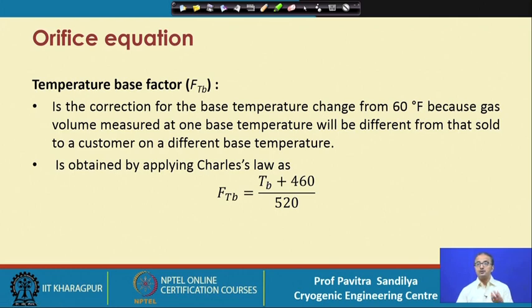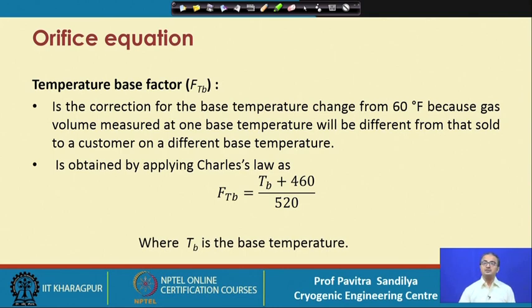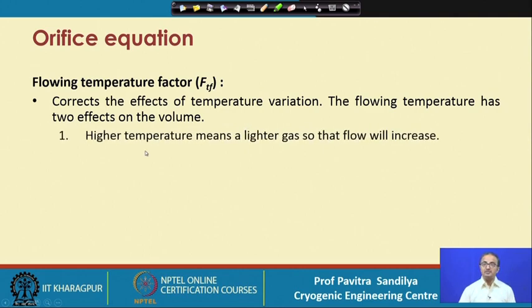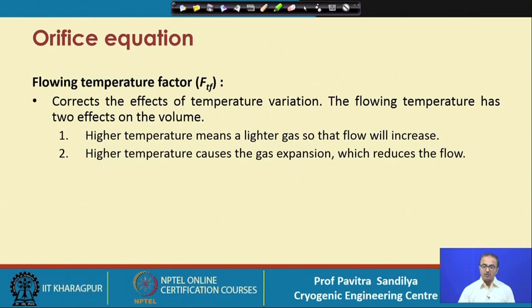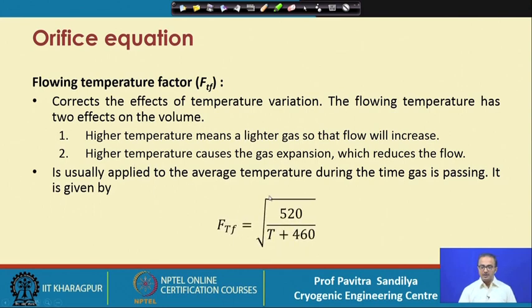Values in the literature are given in the FPS system, so tables are also in FPS — we can later convert units. The flow temperature factor corrects for temperature variation and has two effects: at high temperature the gas becomes lighter, tending to increase flow, but high temperature also causes gas expansion, which reduces flow. This factor is applied to the average temperature during the time gas is passing.